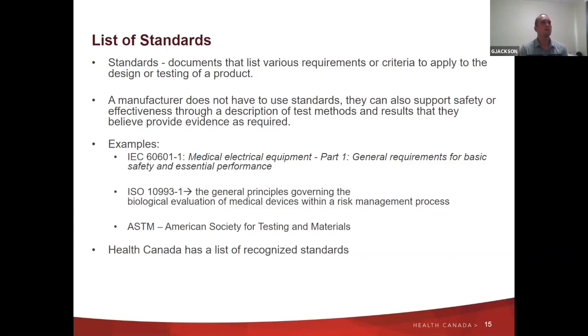Next, a list of standards is pretty common, especially for devices we see in digital health. It's not absolutely required, but usually useful. They can show they've conformed to electrical safety, electromagnetic compatibility standards, and things like that—well-known international standards like IEC 60601, and ISO standards, which we see a lot for biocompatibility and other things. Health Canada has a published list of recognized standards which manufacturers can pick from, applicable to their device that they've tested to or designed towards. Depending on the standard, sometimes we'll take their signed declaration of conformity, and sometimes we require the test reports for additional information—it really depends on the standard and the device type.